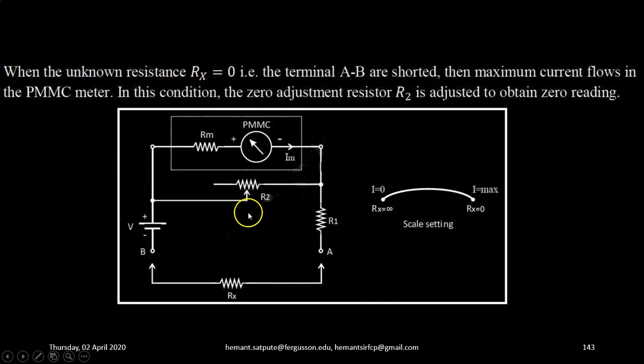When unknown resistance Rx equals 0, that is, terminals A and B are shorted, then maximum current flows in the PMMC meter. In this condition, the 0 adjustment resistor R2 is adjusted to obtain the 0 reading. So here, look at the scale reading. When Rx is 0, this external unknown resistance is 0, then current will be maximum.